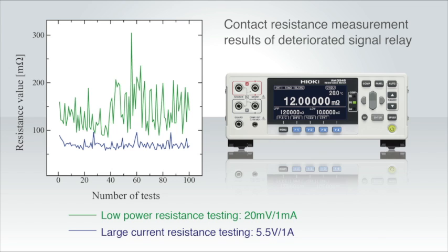as a result of the deterioration of the contact. When measuring a signal contact using a large current or high voltage, the oxide film on the contact can be damaged, temporarily causing the resistance to be small and resulting in a false measurement result.